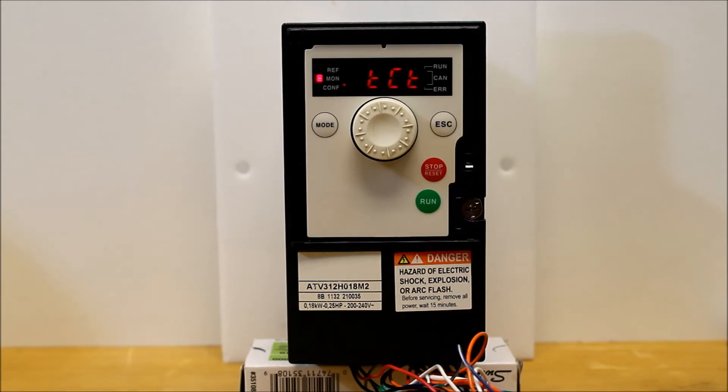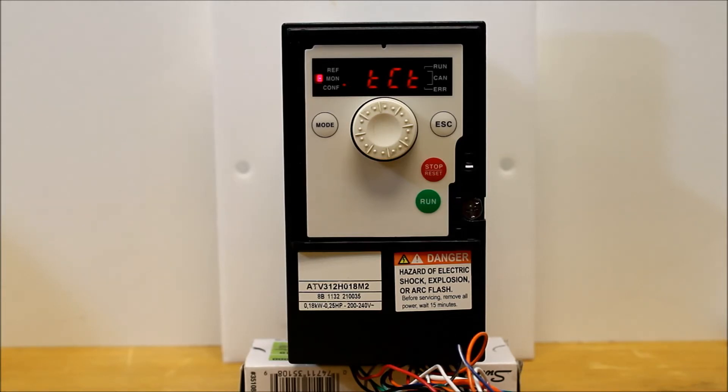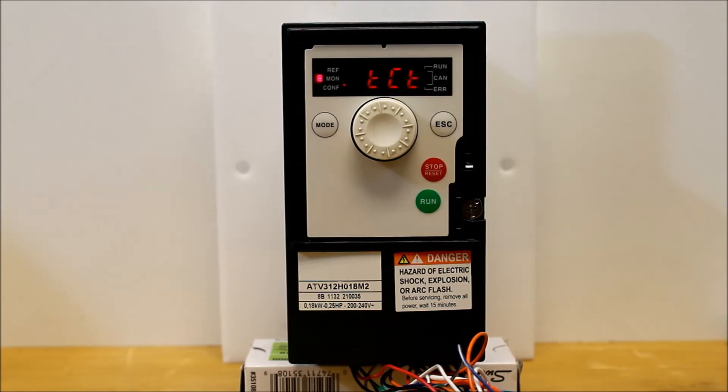From the factory setup as a transition, which means that you actually have to power the drive up first and then toggle your run command. Otherwise, if it gets a run command upon power up, it will go to an NST state, which means that it didn't like the fact that it came with a run command. So you have to turn off your run command if that's the case.